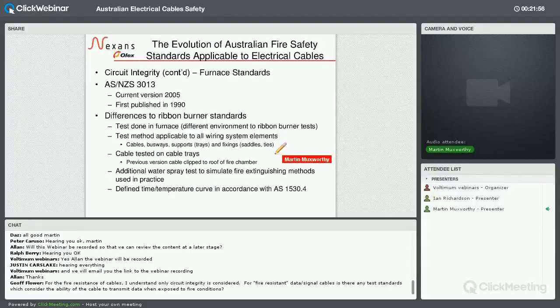And for the cable itself, the current version of the standard requires that the cable is tested on a cable tray. Again, that's to simulate, pretty obviously, the way that a cable would be installed in practice, and I guess it's taken some generations of development of this standard to come to that point. All cables tested as standard must be mounted on a specified cable tray. There's also an additional water spray test, like I'd mentioned with the British standard, to simulate fire extinguishing methods.